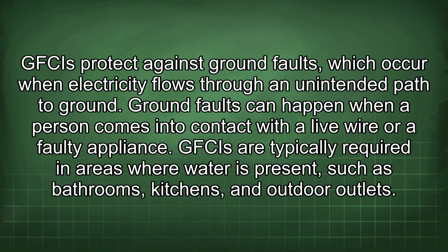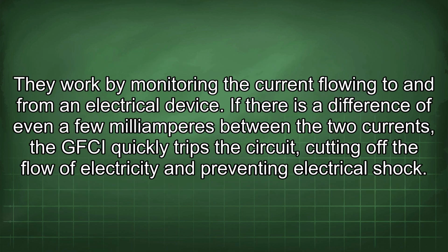Ground faults can happen when a person comes into contact with a live wire or a faulty appliance. GFCIs are typically required in areas where water is present, such as bathrooms, kitchens, and outdoor outlets. They work by monitoring the current flowing to and from an electrical device. If there is a difference of even a few milliamperes between the two currents, a GFCI quickly trips the circuit, cutting off the flow of electricity and preventing electrical shock.